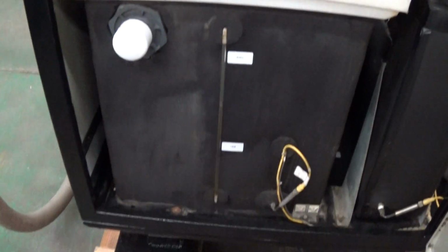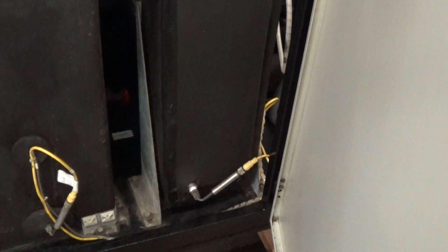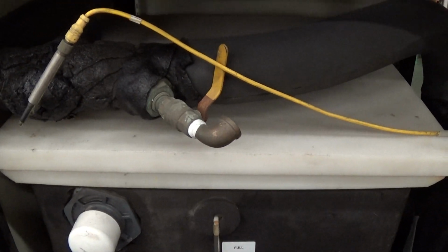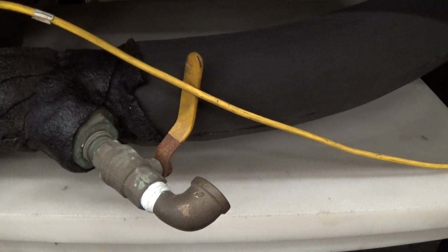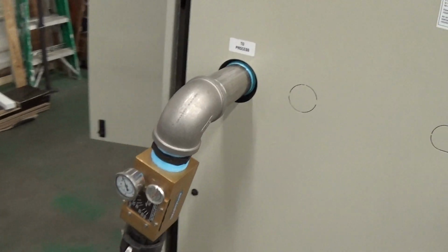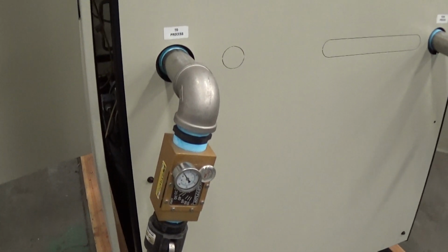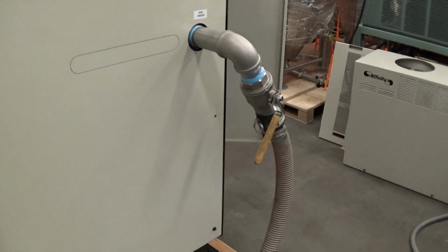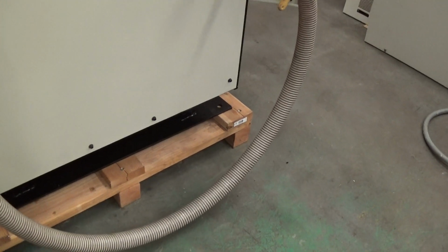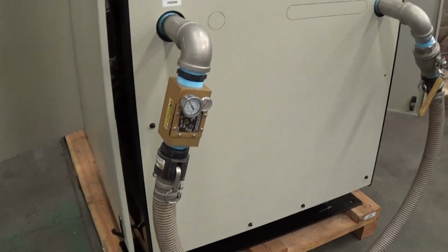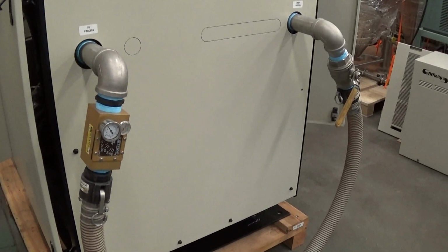Here's your reservoir tank. Little sight glass there, temperature probe. That's your braze plate, fluid to refrigerant heat exchanger. That's just a test drain right there. Leave that in the vertical closed position. The chiller has 2-inch NPT connections. This is just our test loop. We have the unit filled up with about 40% glycol right now. If you're going to run the unit at about a 30-degree set point, we want to see you use 35% glycol solution or 40%. I don't like seeing it much less than that.